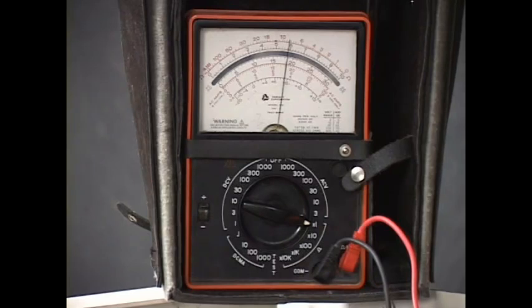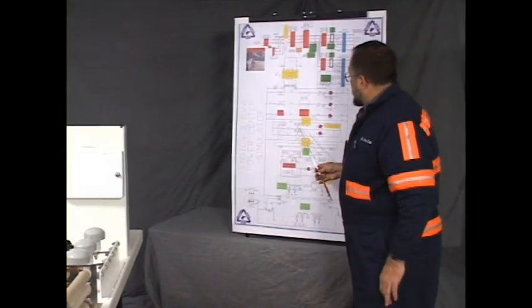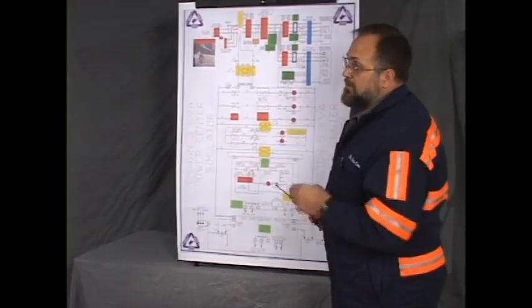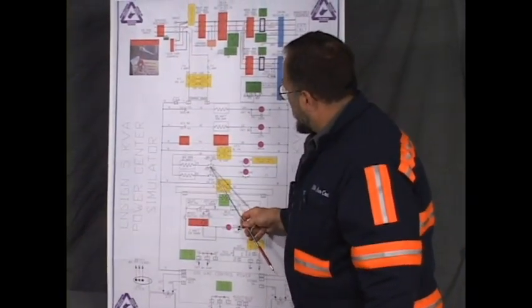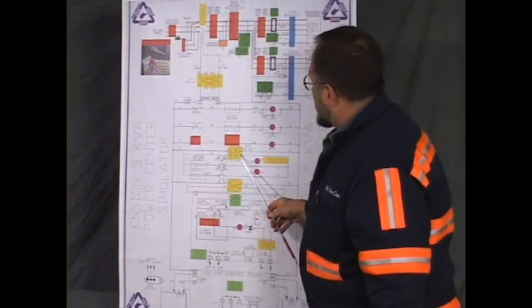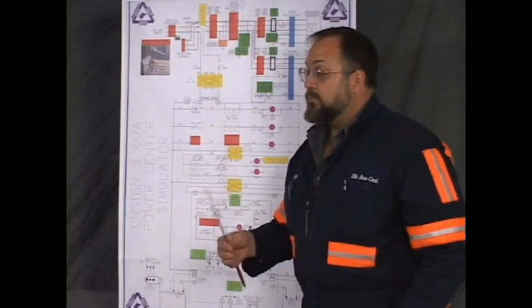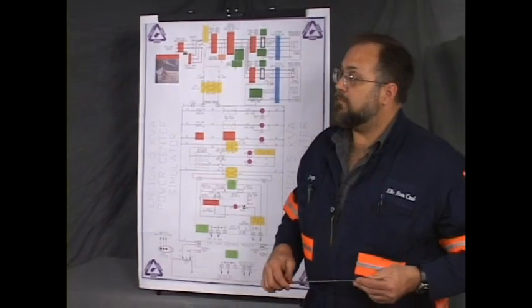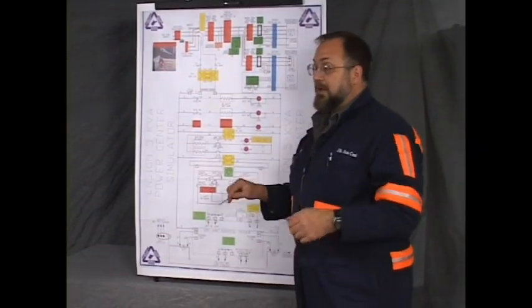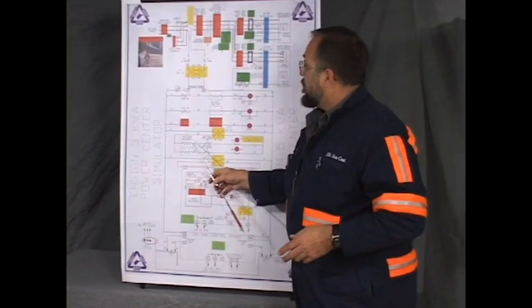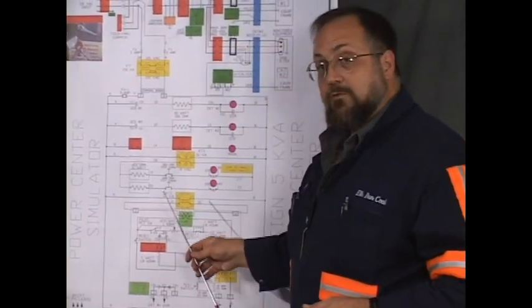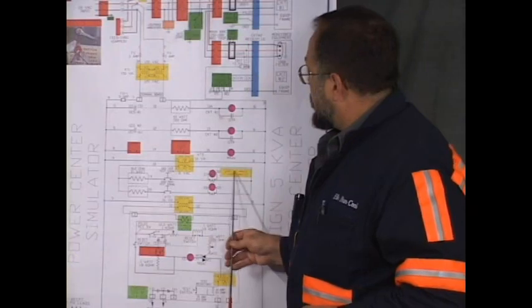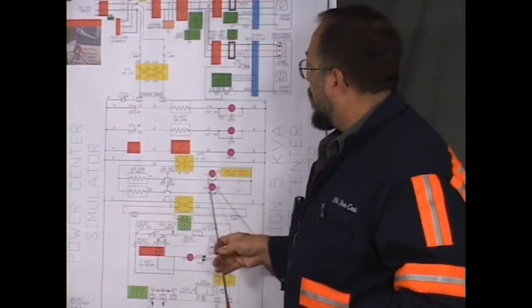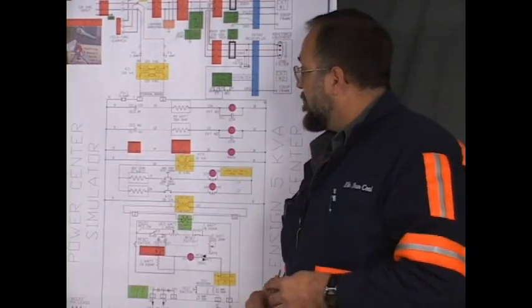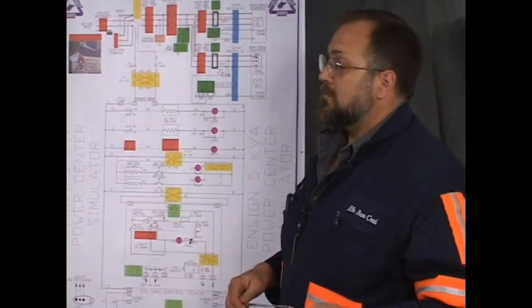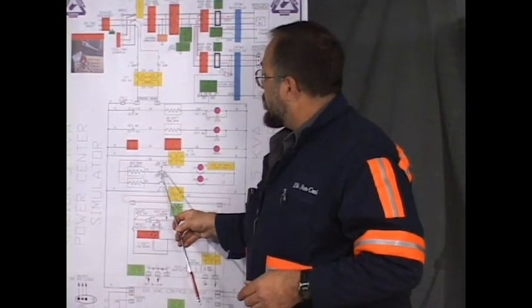It's not completely open, although the print shows this is a normally open switch, but the circuit doesn't read open. The reason that you read that, it's approximately 9 ohms, is if you would follow this circuit back, you'll see that it has a path, a parallel path. And an ohm meter is not unidirectional. You can't more or less aim your ohm meter. When you attach it to a point, it's going to read any path it can take. And in this circuit, if you look at the drawing, you'll have a parallel path. Now, the value of this resistor is listed as 8.2 ohms, and you have the wire involved as well, and you have this little transformer, KT3, and that accounts for the 9 ohms that is shown by the meter. We're reading an open switch with 9 ohms.